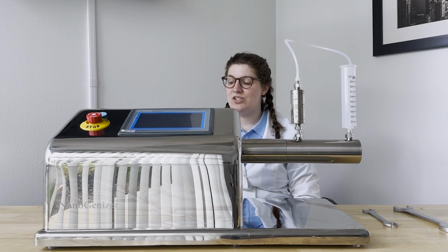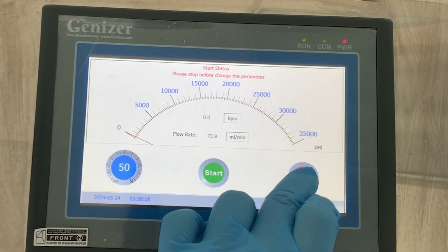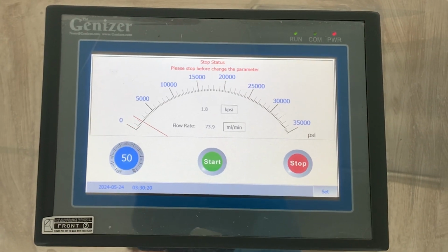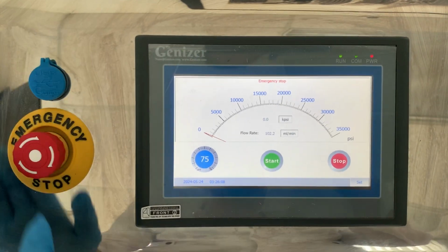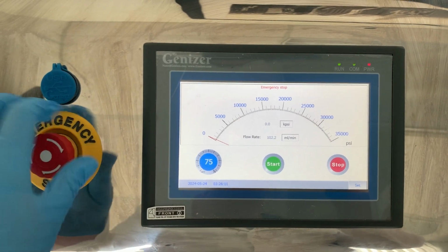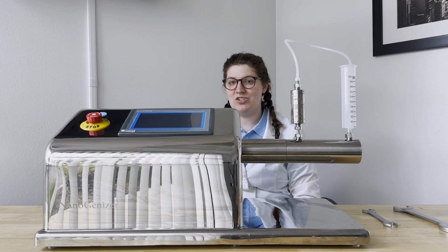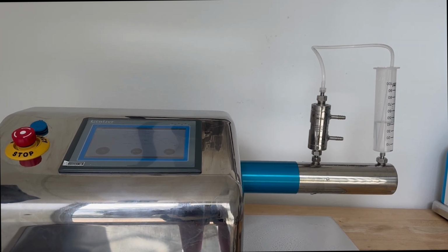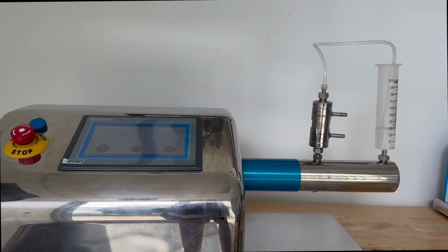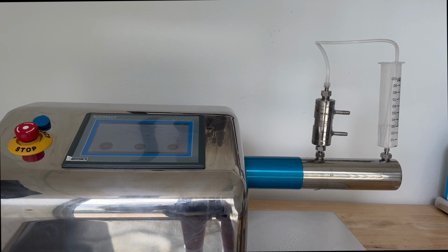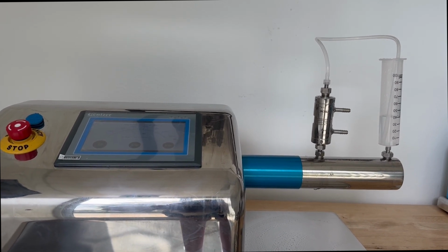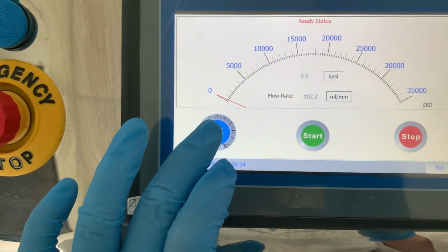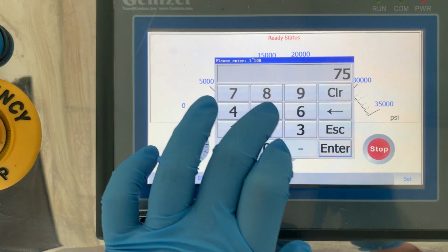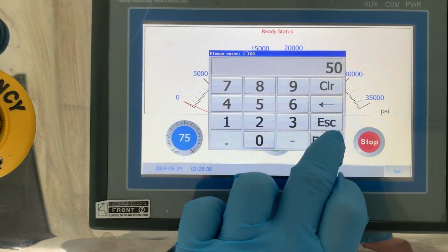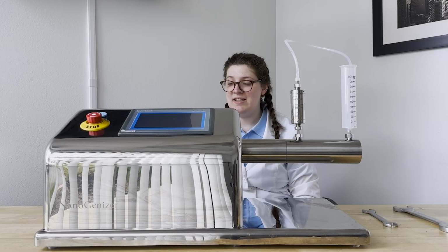For instance, start and stop, as well as error messages. If you see this message, the emergency stop is on. You can twist it to end the emergency stop. Now, add a solvent to the machine and run through at a very low speed and pressure. This will confirm the machine is working before moving to higher pressures. On the lower left of the screen is the percent speed. Use this to determine the pressure. You may need to try several speeds to get to your desired pressure.